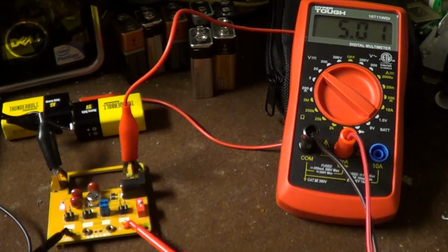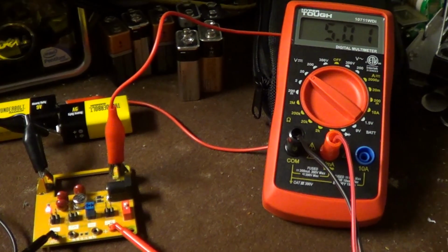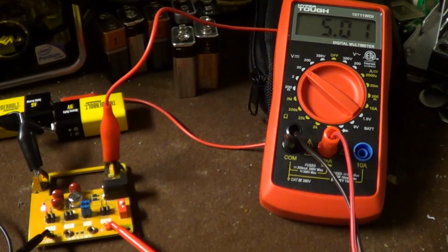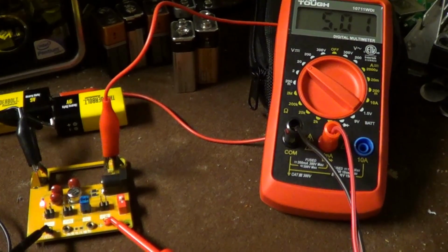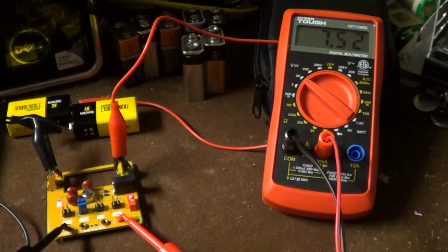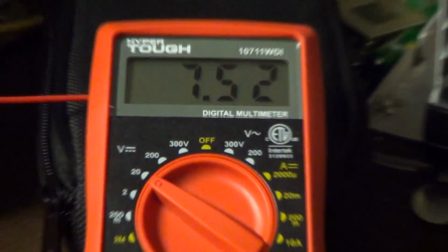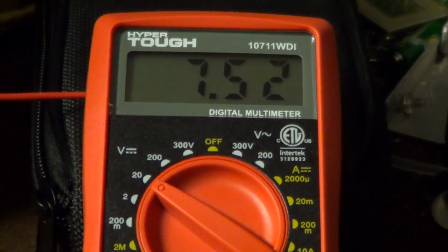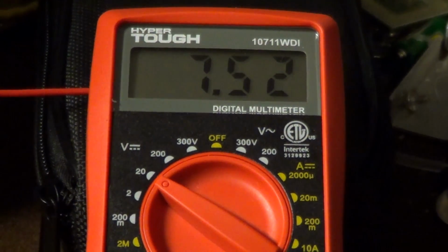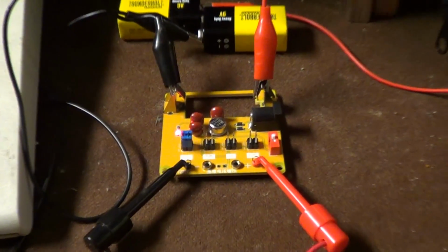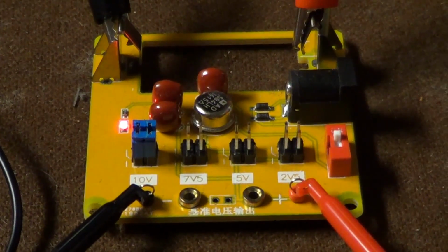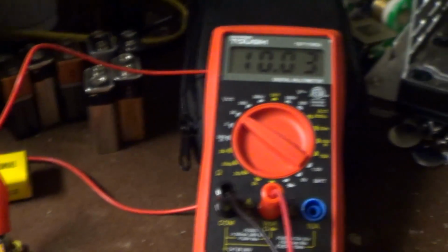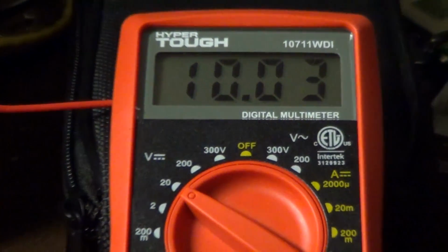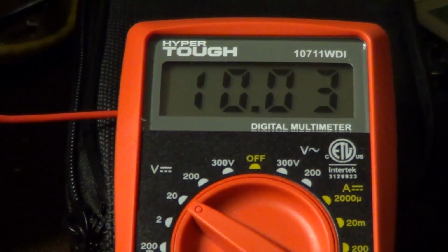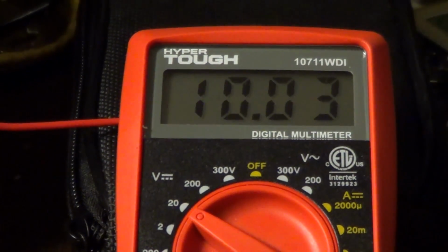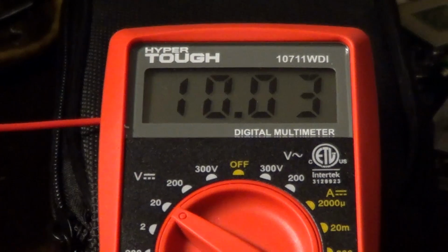Things are now at 5 volts DC output from the precision voltage reference, after letting it stabilize again. The reference has now been set to output 7.5 volts, and again the meter gives a very accurate result, well within its specifications. Finally, here's the 10 volt setting, and again it's extremely close to perfectly accurate, if not dead on. I'm certainly not going to quibble over a tiny digit's worth of precision.